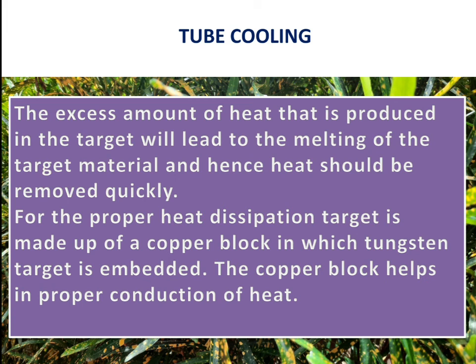For proper heat dissipation, the target is made up of a copper block in which a tungsten target is embedded. The copper block helps in proper conduction of heat. The anode of the x-ray tube is made up of a copper block with the tungsten button embedded in it. Copper is used because of its very good heat conductivity, allowing heat produced in the target to be conducted and transferred to the external environment.